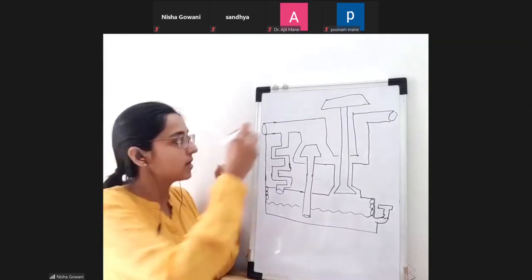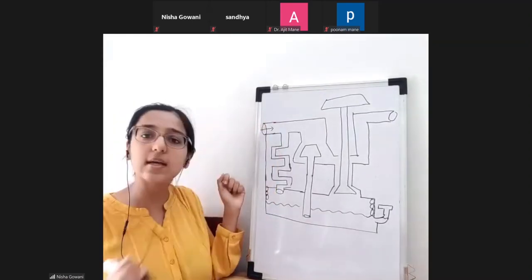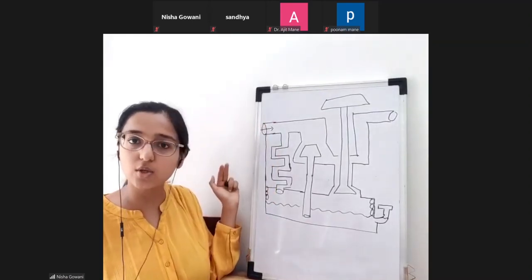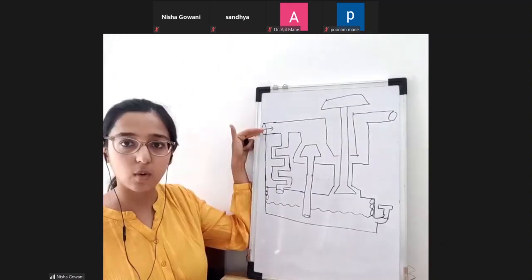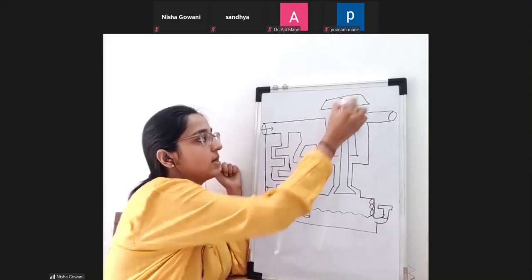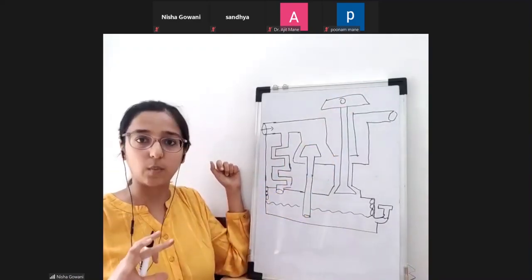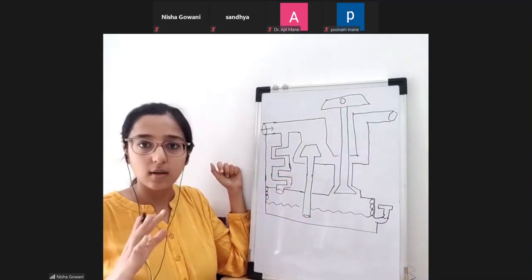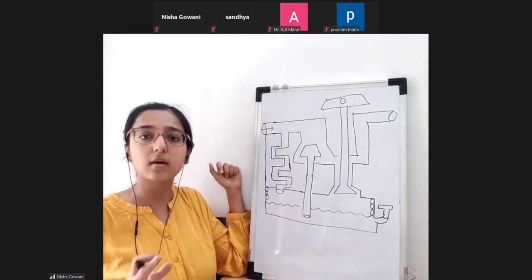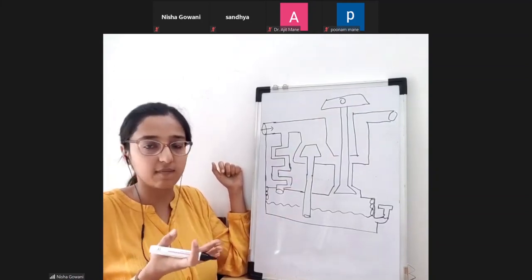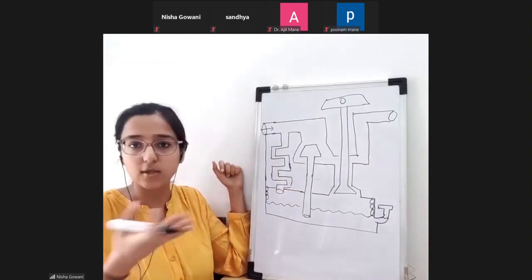So we have something known as the inlet. This is the inlet where the fresh gas comes, so your oxygen nitrous mixture arrives over here. Now, I have kept the dial at 0. It means there is going to be no vapors joining. The vaporizer is not going to give any isoflurane. Suppose this is isoflurane, no isoflurane is joining.